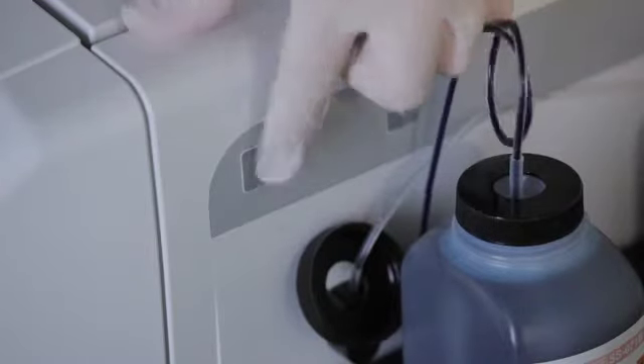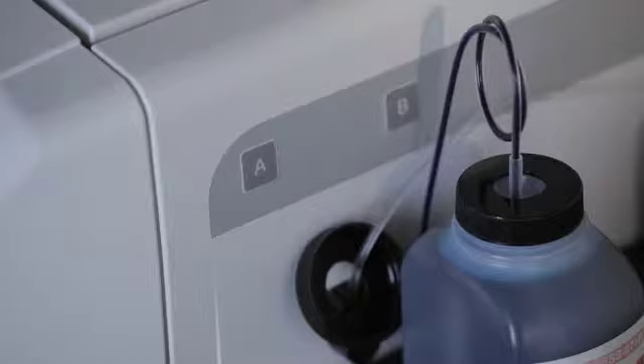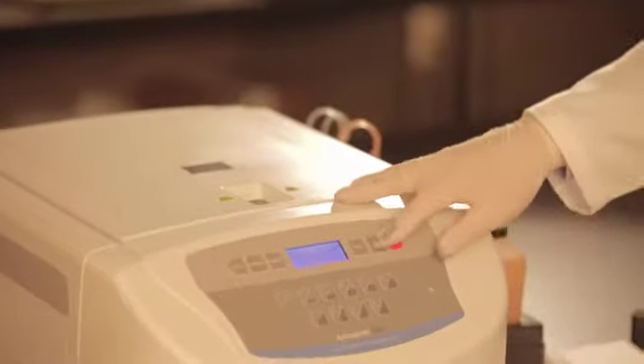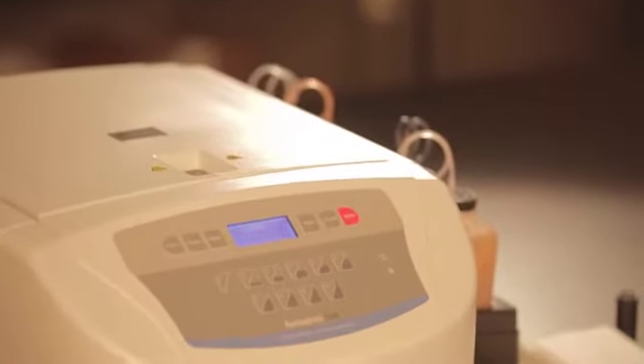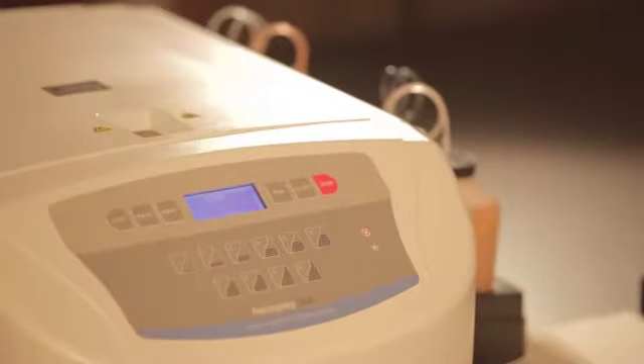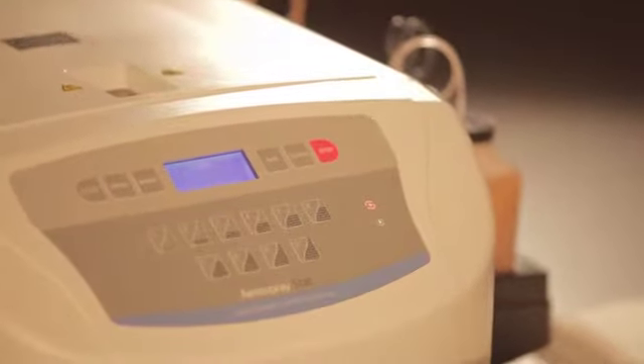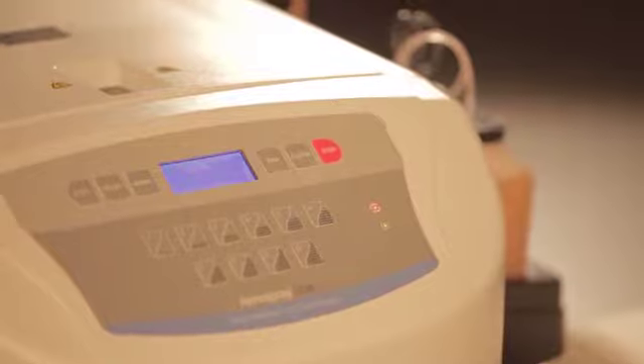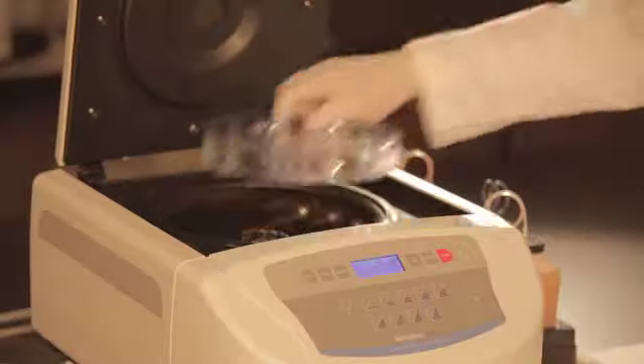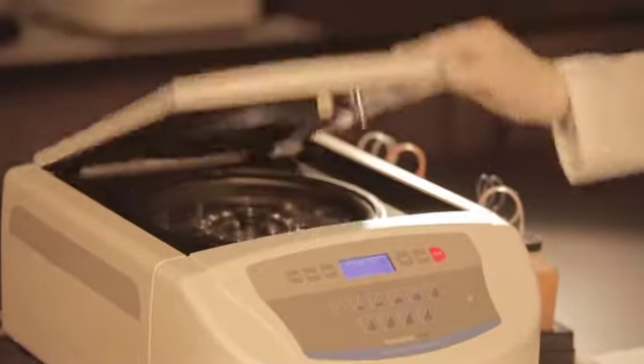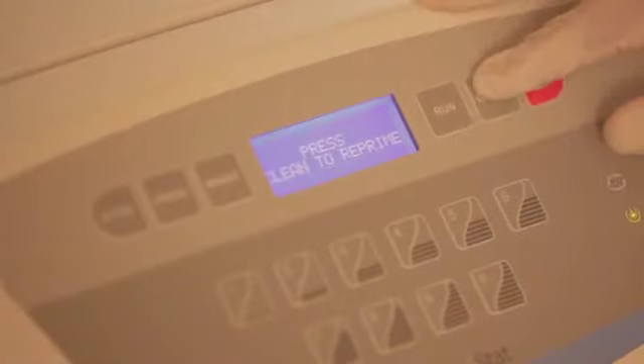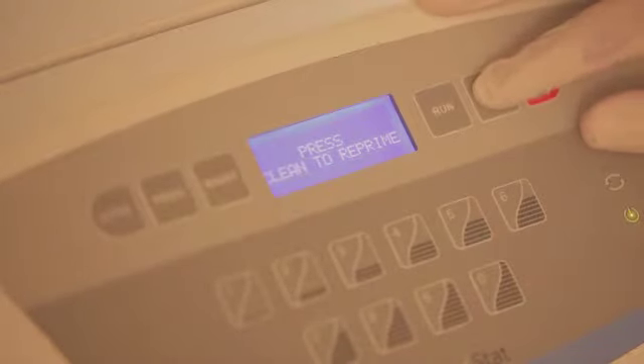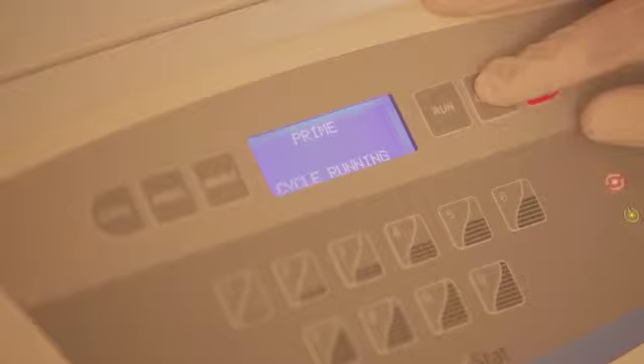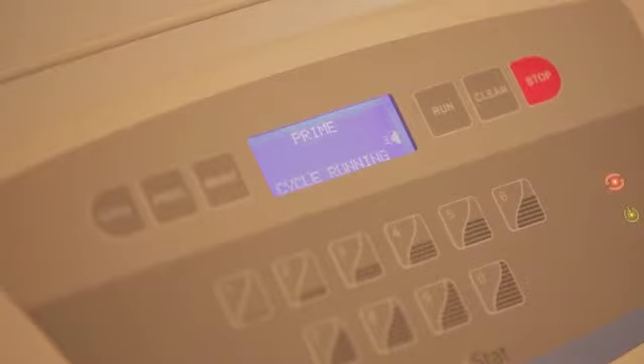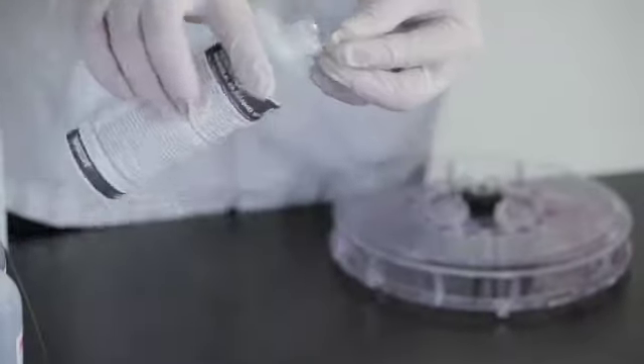If the prime button is pressed after a stain cycle was started but not completed, a warning will appear on the screen when Run is pressed. Users are instructed to run a clean cycle in order to replace the methanol in the nozzles at the beginning of the stain cycle, as it should be. Preventive maintenance for the Hematology Pro Stainer is as previously described, except that a system clean cycle should be run at the end of each shift, or if the stainer will sit idle for more than 4 hours. A carousel clean cycle should be run each day.